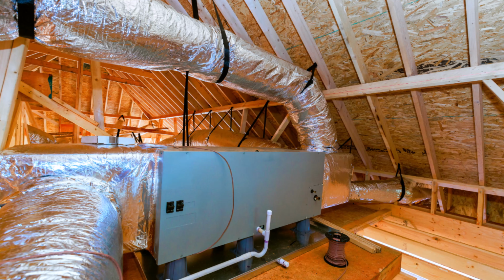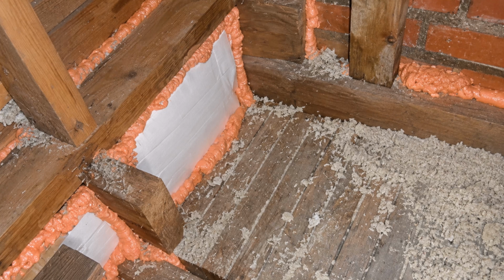I was inspecting a bonus room a while back where the homeowner was convinced they needed a new HVAC system. The room was miserable every summer. We opened the knee wall access door and looked behind the wall, and every floor cavity was completely open to the attic. We sealed those cavities, air sealed the knee wall, and the room became dramatically more comfortable without replacing a single piece of HVAC equipment.